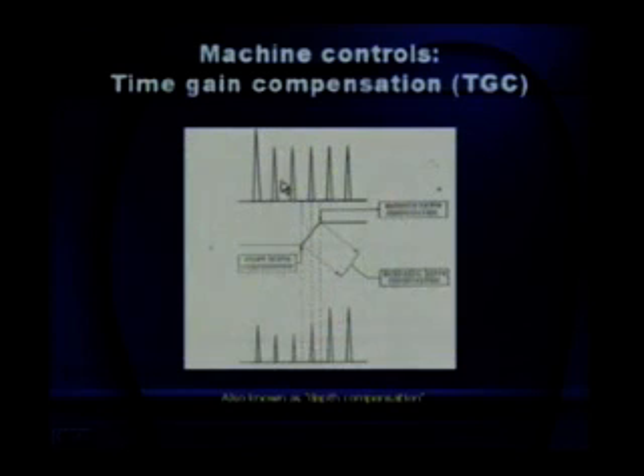There's an example here. These are the echoes coming from the tissue. This is the position of different levers. On this side we have increased the gain compensation, and here we have decreased. So as a result, these echoes are reduced in intensity and these echoes are enhanced. So that is how we selectively modify the image that is being displayed on the monitor.